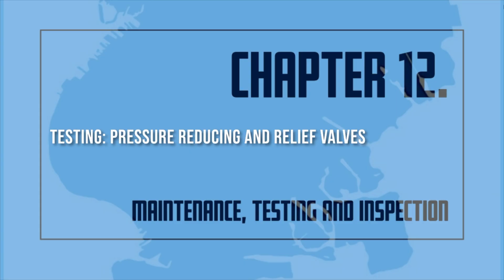Pressure reducing and relief valves. Sprinkler systems. At 5-year intervals, a full flow test shall be conducted on pressure reducing valves and shall be compared to previous test results and the results from the original installation or acceptance test. Annually, a partial flow test shall be conducted with a flow rate great enough to lift the valve seat. Section 12.5.1.3 of the National Fire Protection Association No.